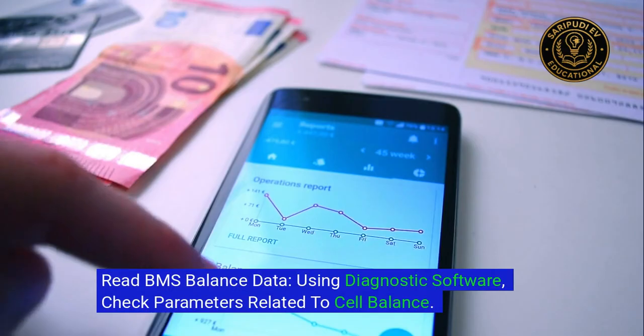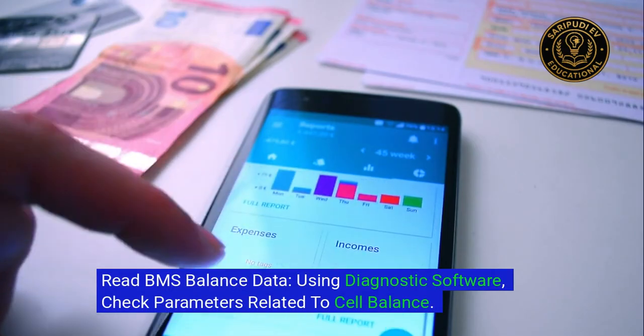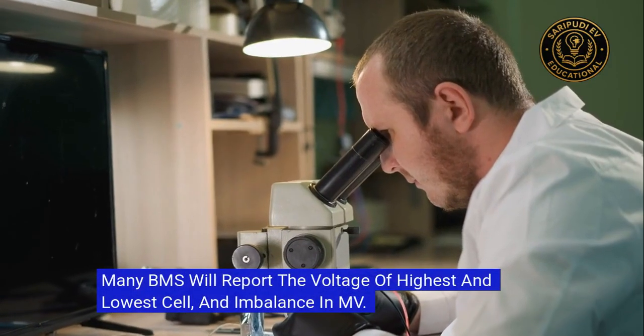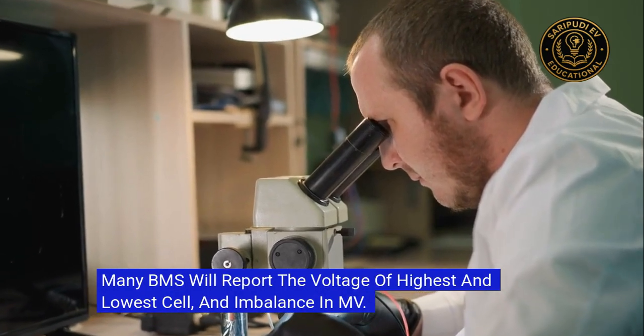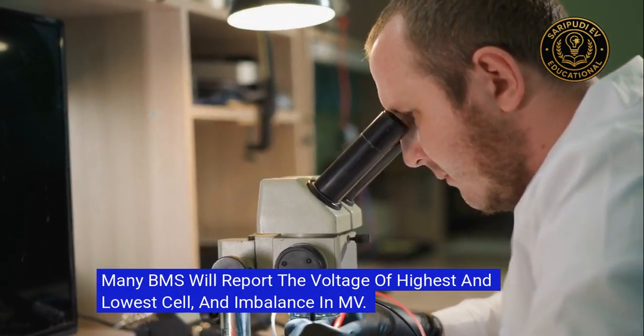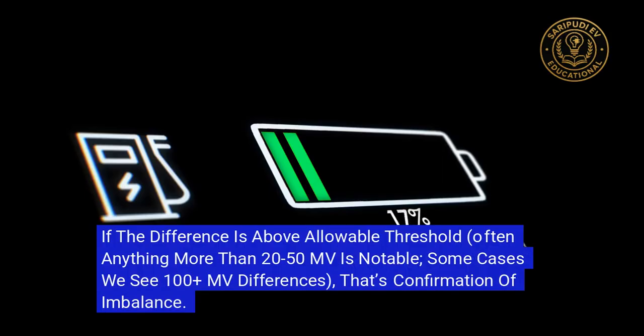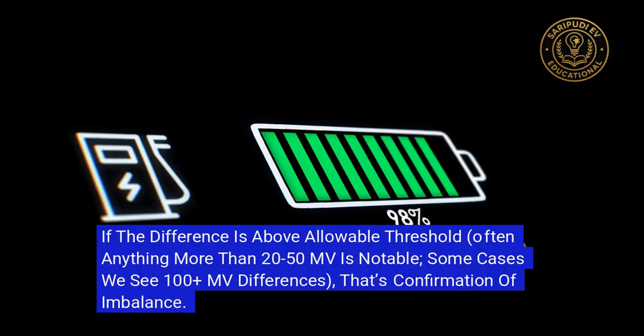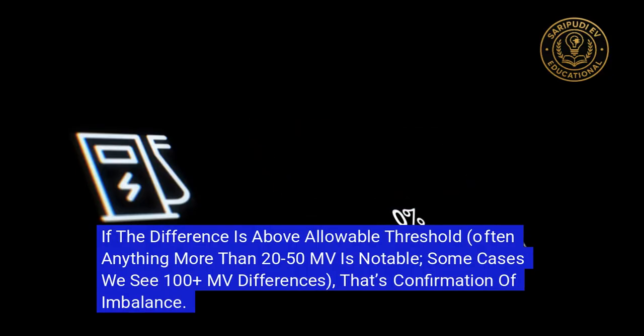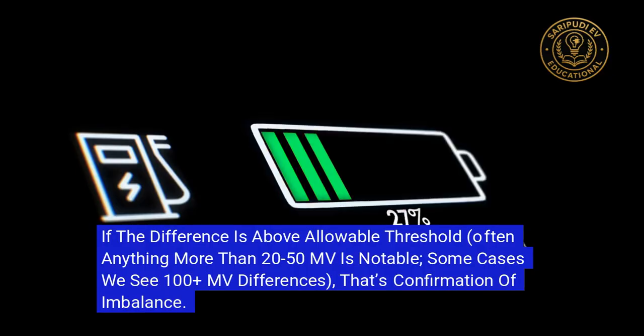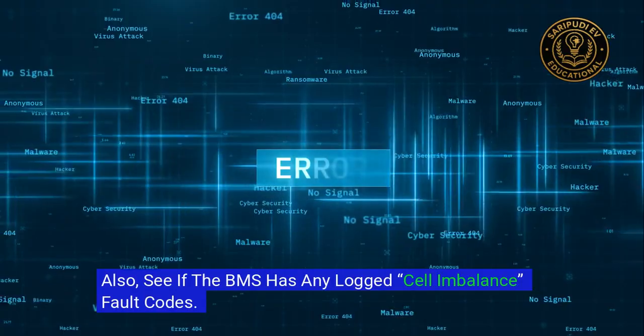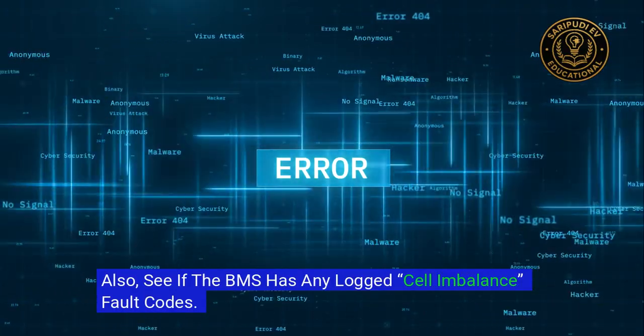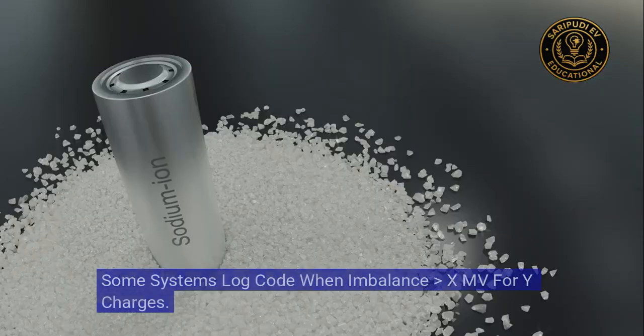Using diagnostic software, check parameters related to cell balance. Many BMS will report the voltage of the highest and lowest cell, and the imbalance in mV. If the difference is above the allowable threshold, often anything more than 20-50 mV is notable. In some cases we see 100-plus mV differences, that's confirmation of imbalance. Also, see if the BMS has any logged cell imbalance fault codes. Some systems log a code when imbalance is greater than X mV for Y charges.